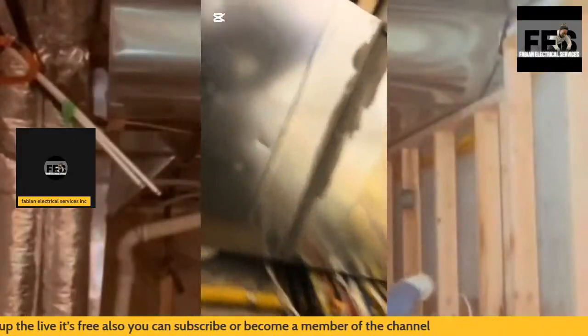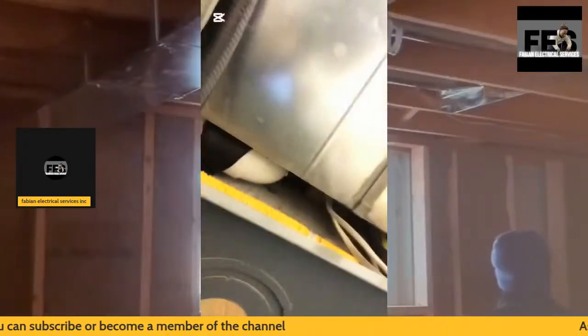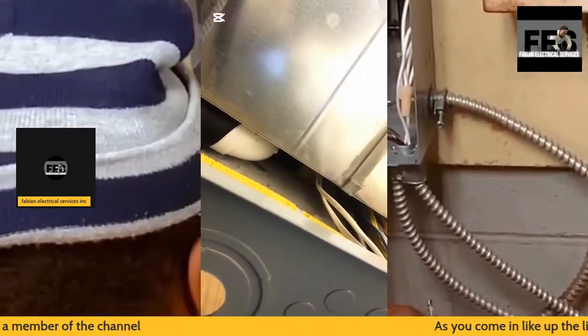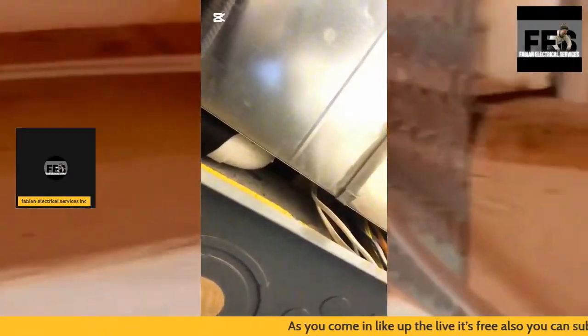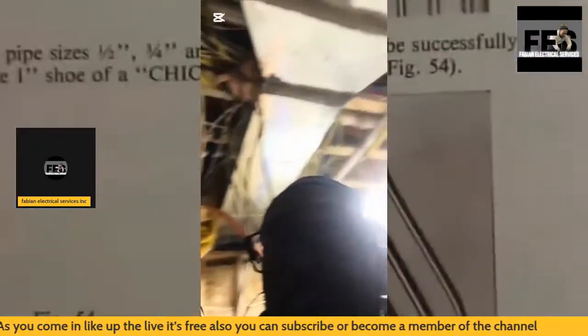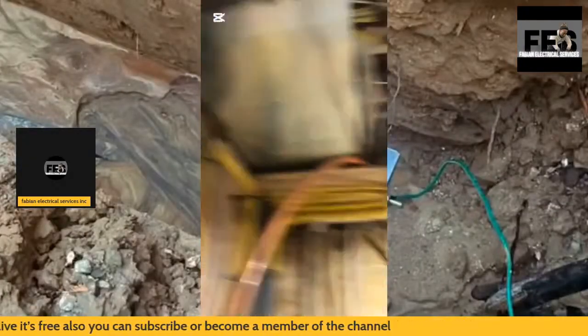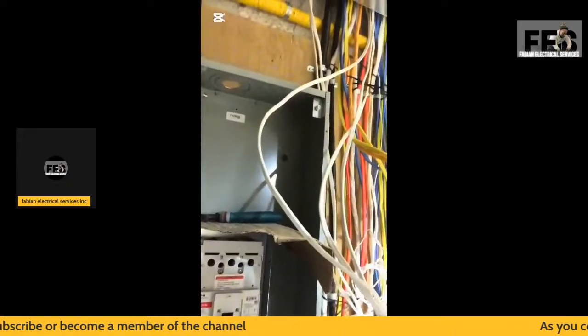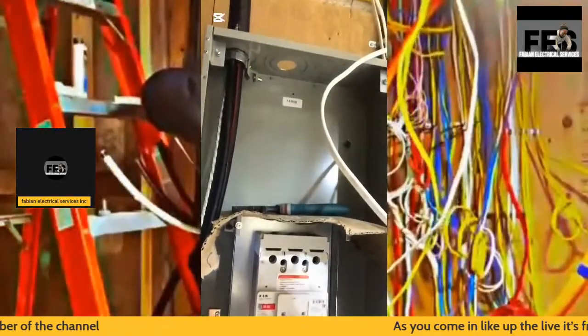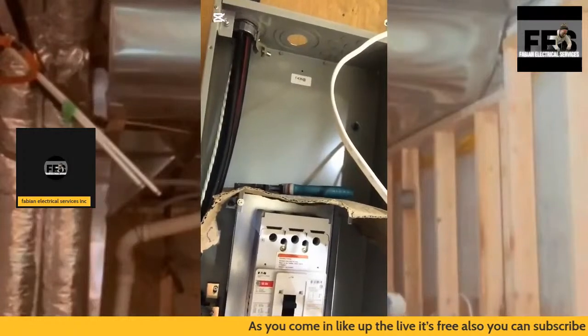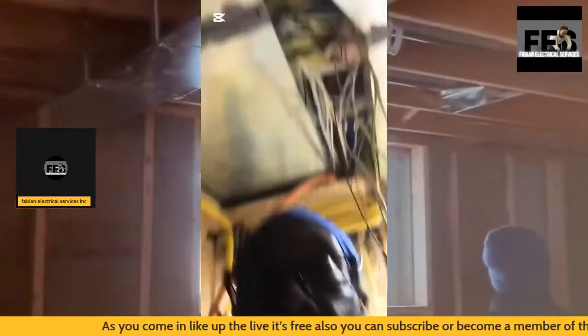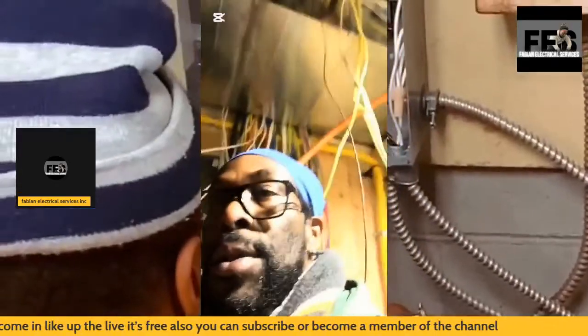As you can see, this is a pretty big job. You can also see the wires touching the duct — that has to be addressed within code compliance, so I'll place some insulation between my wires and the duct to stay within code. Many of you might ask what happens if the inspector comes and the job isn't ready for inspection — you'll simply have to rebook your inspection because you've wasted the inspector's time. So it's best to have everything prepped and ready to go.